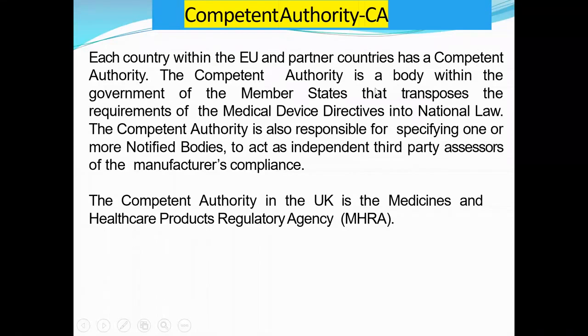The competent authority is a body within the government of the member state that transposes the requirements of the medical device directives into national law. So the competent authority is also responsible for specifying one or more notified bodies to act as independent third party assessors of the manufacturer's compliance. Now, the competent authority in the UK is the UK MHRA.